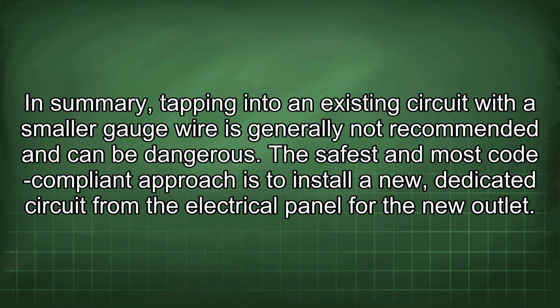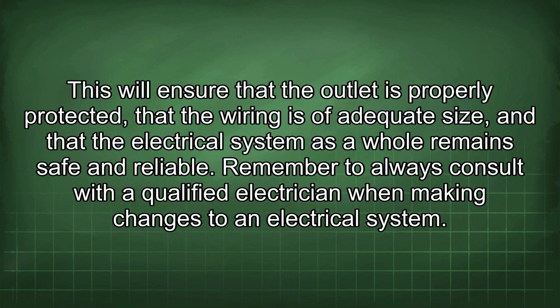In summary, tapping into an existing circuit with a smaller gauge wire is generally not recommended and can be dangerous. The safest and most code-compliant approach is to install a new, dedicated circuit from the electrical panel for the new outlet. This will ensure that the outlet is properly protected, that the wiring is of adequate size, and that the electrical system as a whole remains safe and reliable. Remember to always consult with a qualified electrician when making changes to an electrical system.